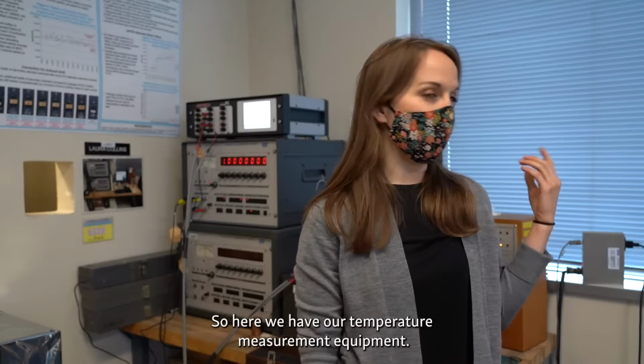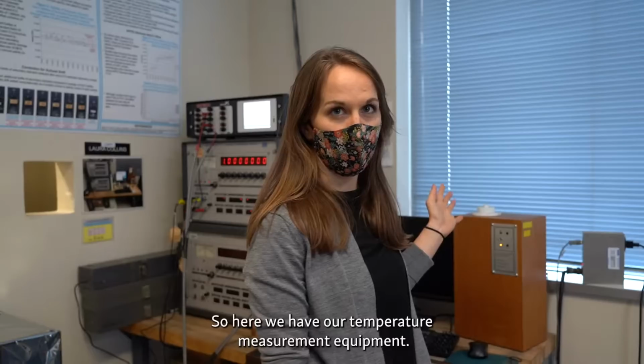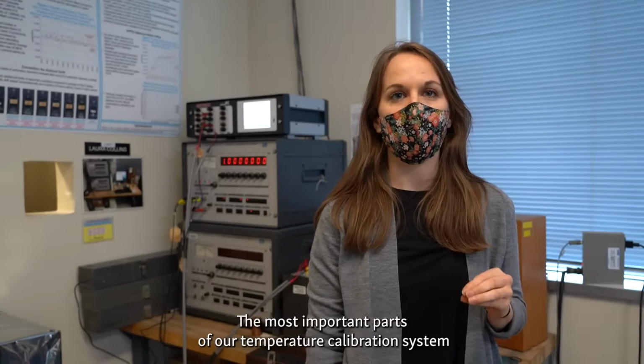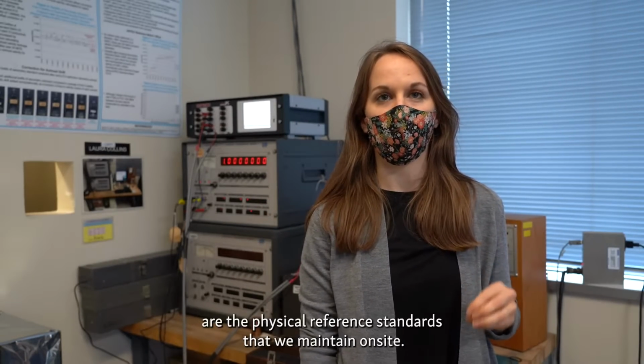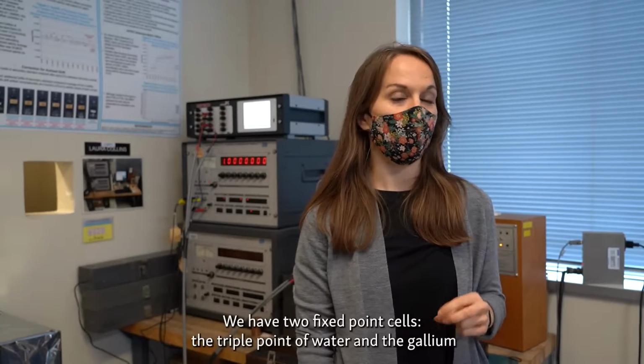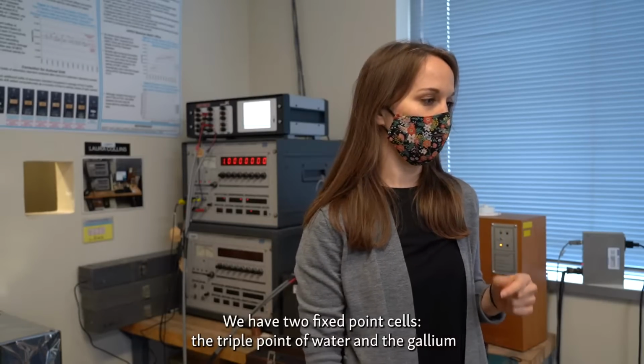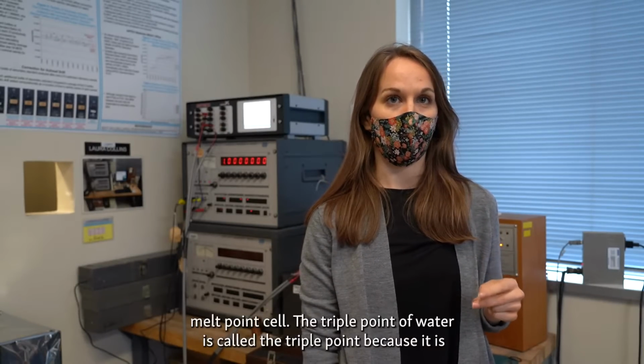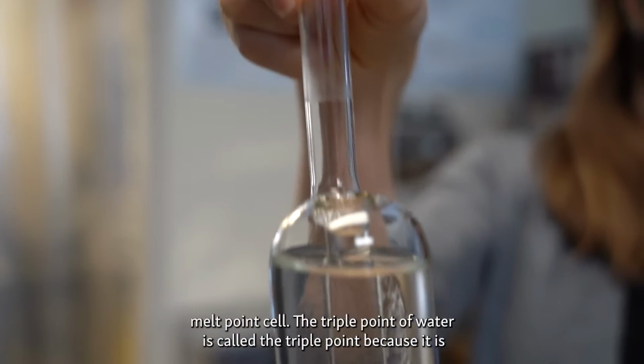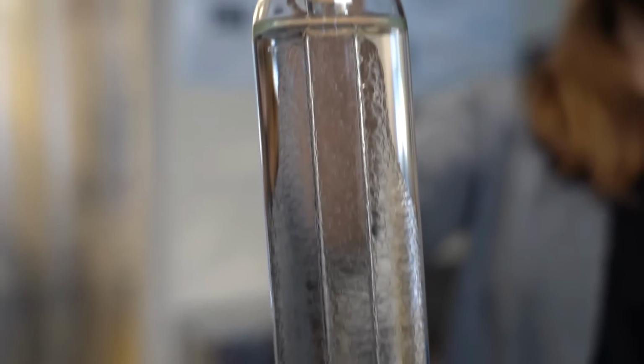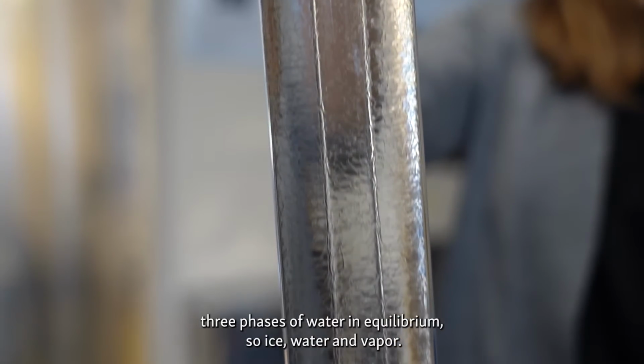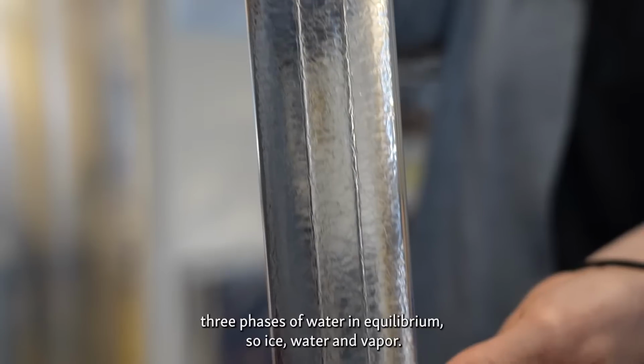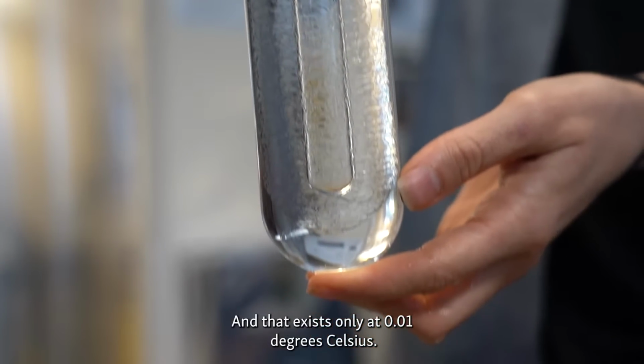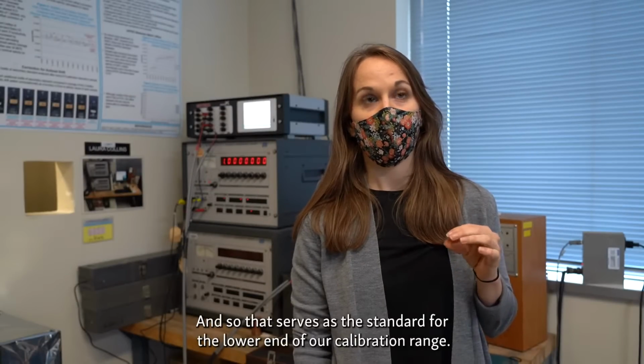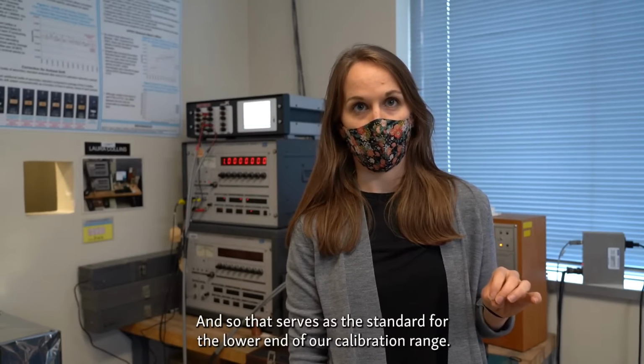So here we have our temperature measurement equipment. The most important part of our temperature calibration system are the physical reference standards that we maintain on site. We have two fixed point cells, the triple point of water and the gallium melt point cell. The triple point of water is called the triple point because it is 3 phases of water in equilibrium, so like ice, water, and vapor, and that exists only at 0.01 degrees Celsius, and so that serves as the standard for the lower end of our calibration range.